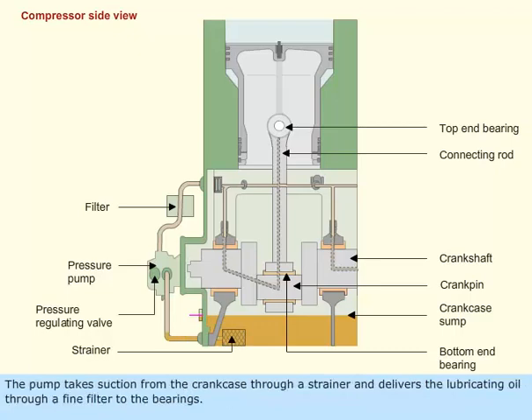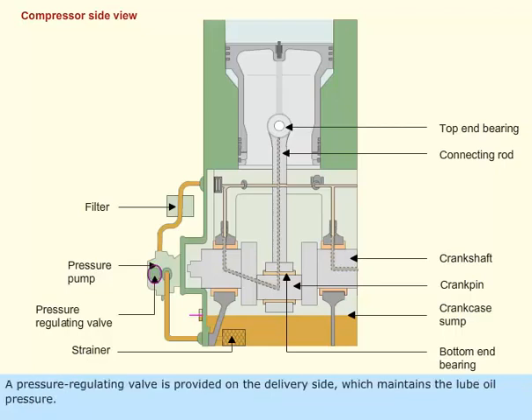The pump takes suction from the crank case through a strainer and delivers the lubricating oil through a fine filter to the bearings. A pressure regulating valve is provided on the delivery side which maintains the lube oil pressure.